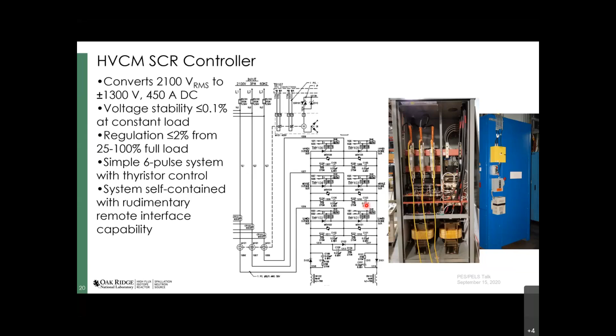Then we come to the modulator system proper. This is what it looks like. There is a stainless steel and aluminum enclosure. This is where all the devices that are operating in air are located, and that's primarily for personnel safety. These operate at plus or minus 1200 volts, and we switch currents that can approach 4,000 amps through some of these IGBTs, so there's quite a personnel hazard. Also inside there is a large energy storage capacitor bank in the back, and I'll show you that shortly.